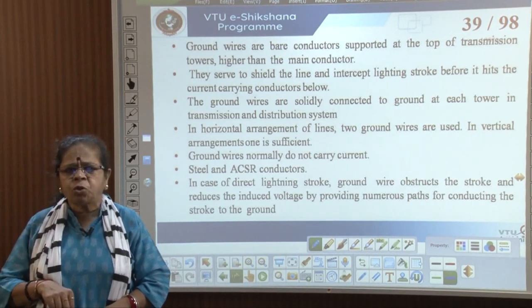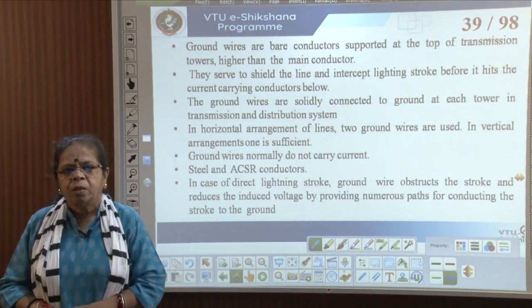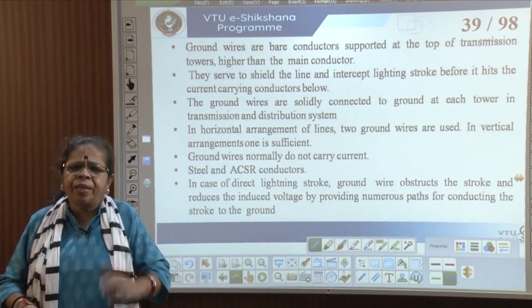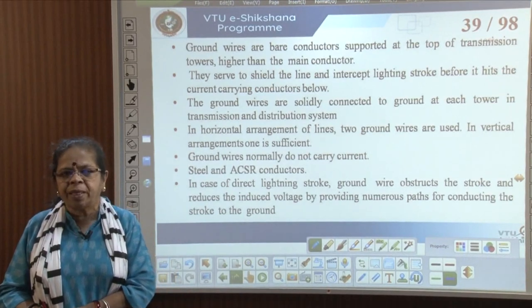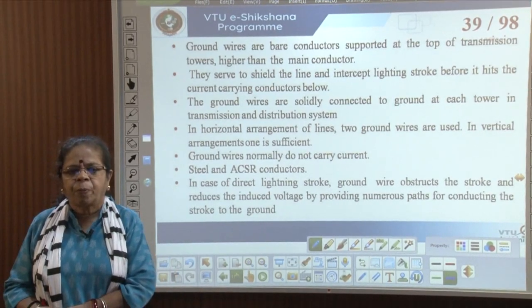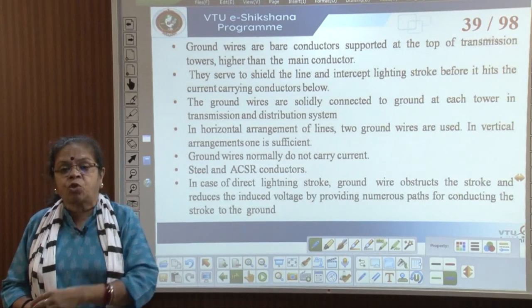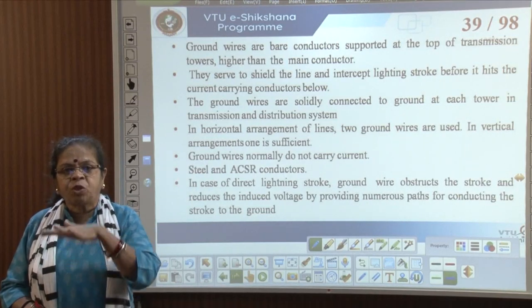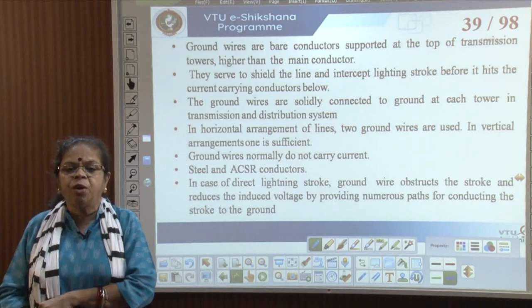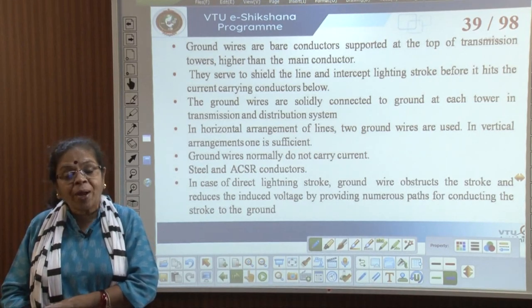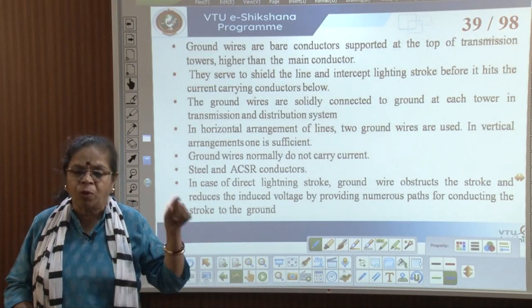Ground wires normally carry no current — they are meant for protection only. Steel and ACSR conductors can be used for ground wires. When there is a direct lightning stroke, the ground wire obstructs the stroke, reduces the induced voltage, and provides numerous paths for conducting the stroke to the ground.